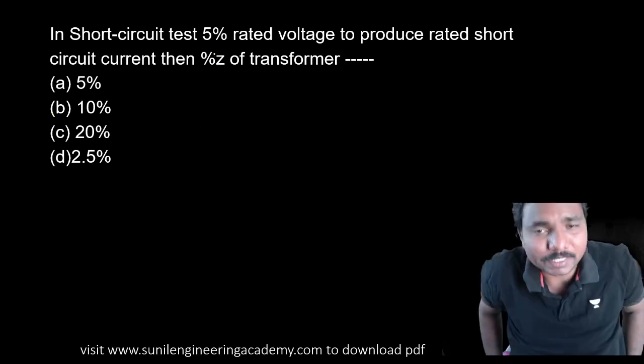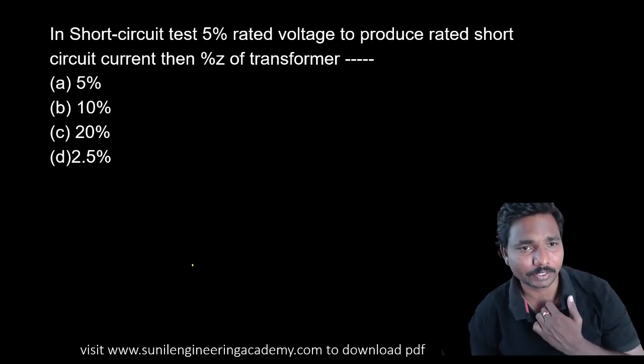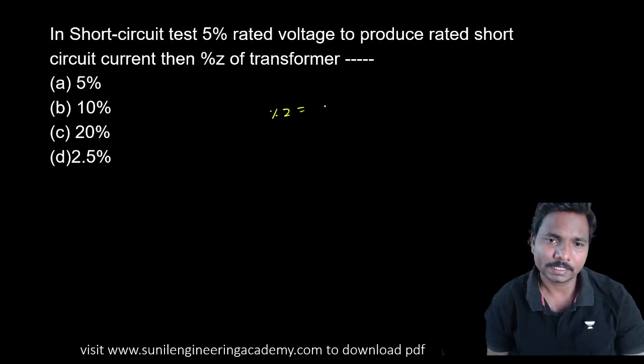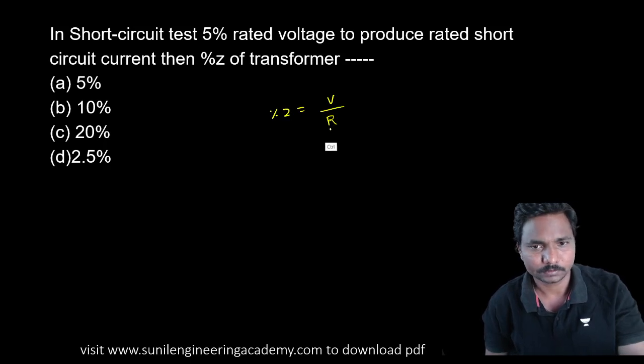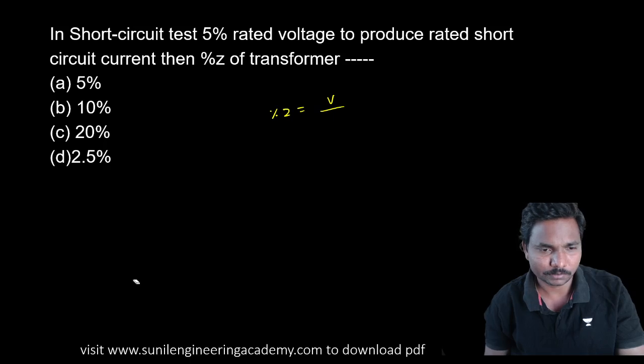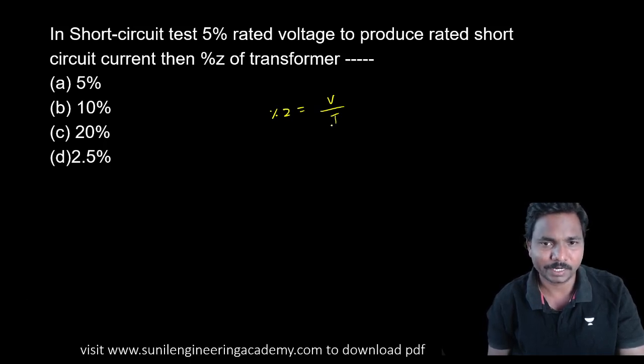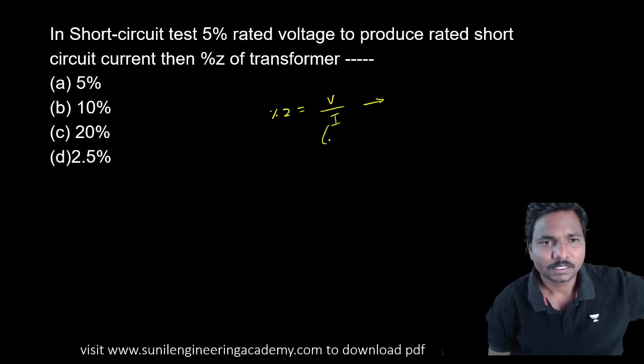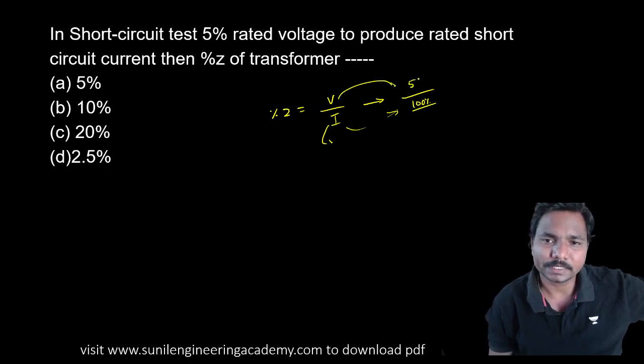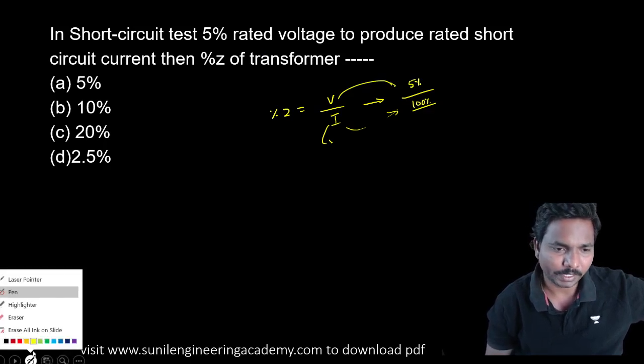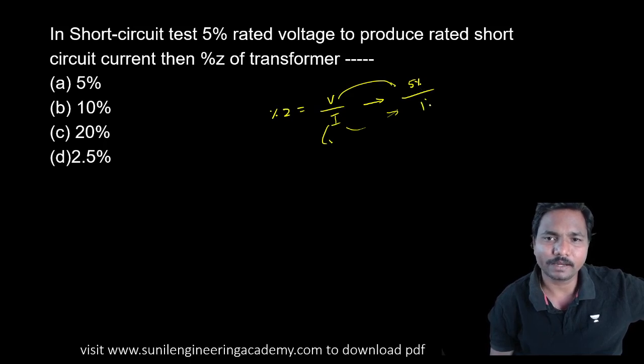In the short circuit test, 5% rated voltage produces the rated short circuit current. Then what is the percentage Z? Z is nothing but the voltage by current ratio. The short circuit test always has to be operated at rated current condition. So we have to get 100% rated current, which we take as 1, and the voltage applied is 5%. So 5% voltage is enough to produce the rated short circuit current, which means percentage Z is 5%.